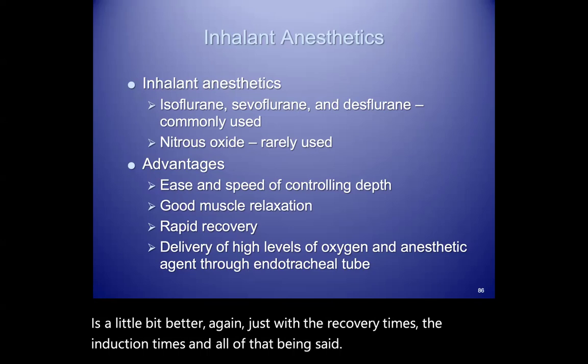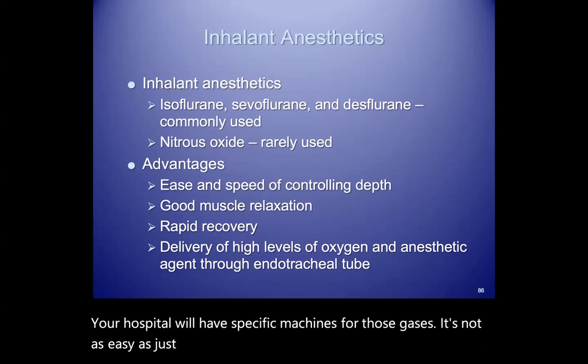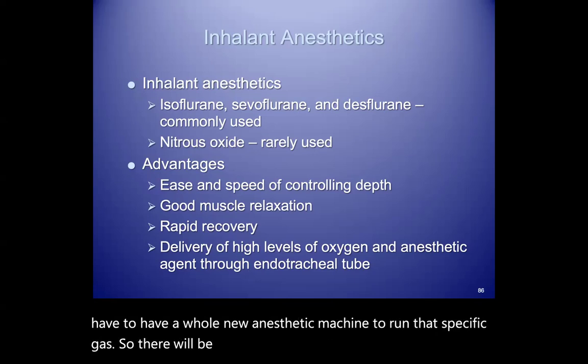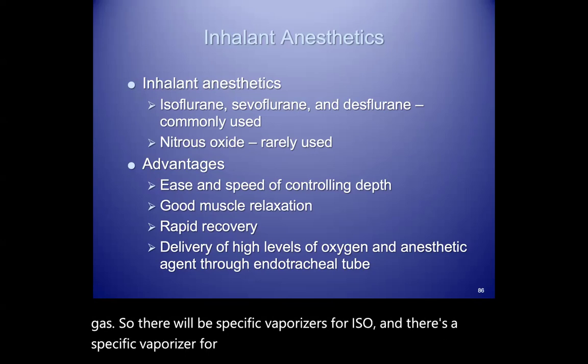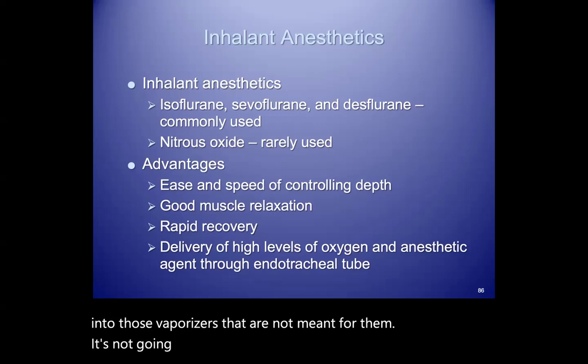That being said, your hospital will have specific machines for those gases. It's not as easy as just buying the different gas and switching it over. You have to have a whole new anesthetic machine to run that specific gas. So there will be specific vaporizers for ISO, and there's a specific vaporizer for Sevo. And you cannot mix those two gases into those vaporizers that are not meant for them. It's not going to dose the patient correctly or safely.